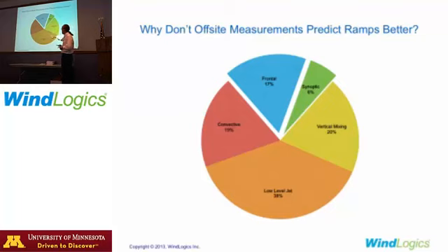But the vast majority of the ramps that we see, this is an analysis of all the wind ramps from a major wind site, are driven by these vertical issues: convective things like thunderstorms, vertical mixing. How quickly does that change over the day, as in the example I showed you? A low-level jet: when does it set up so those really high-speed winds from above come down so low they start getting into the turbine-swept area? Those you just can't do with ground-mounted measurement sensors, unless you put in those really expensive LiDAR and radar profilers, but it gets pretty expensive.